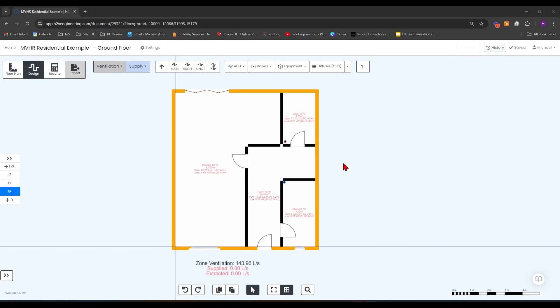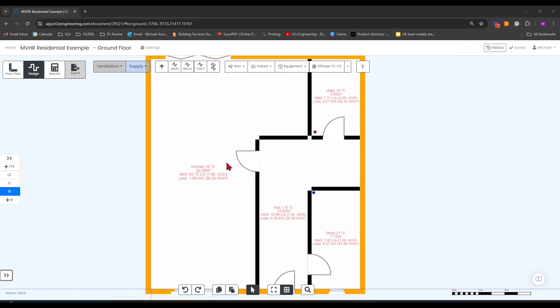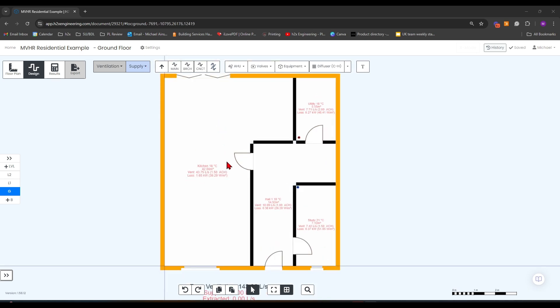In this video we're going to be working through a residential MVHR design. Based on our zone ventilation which is calculated as part of the heat loss room plan, based on either the building regs Part F or CIBSE guides, this will give you a flow rate requirement for each room.